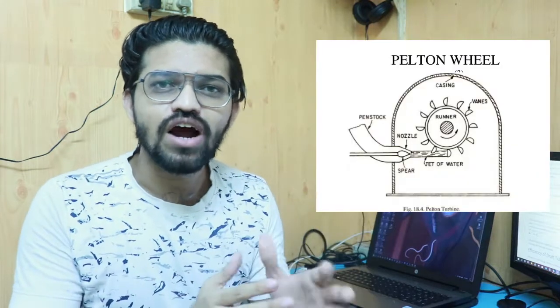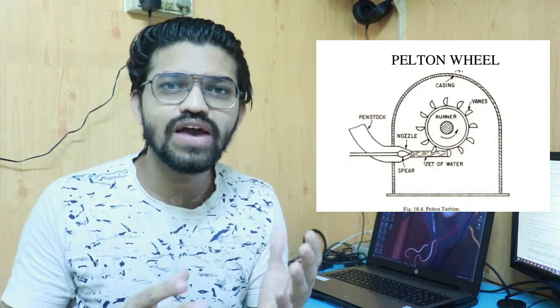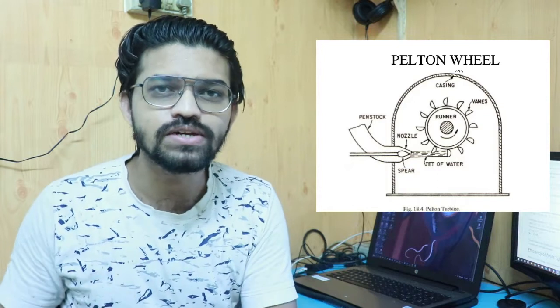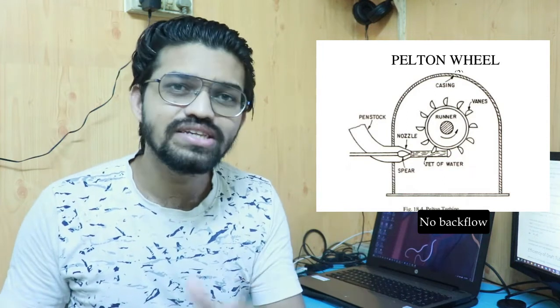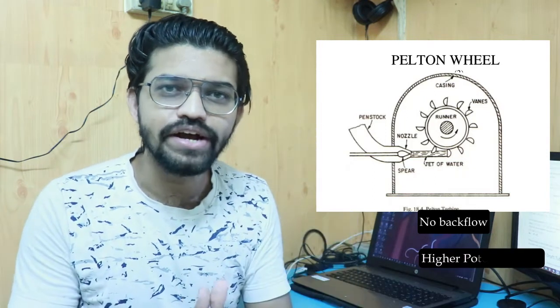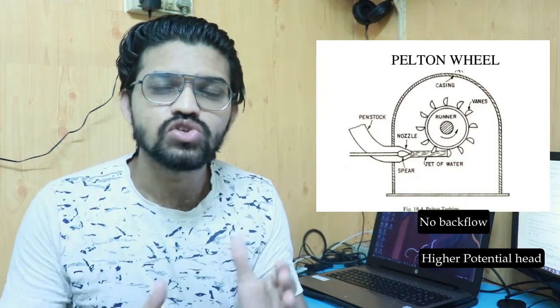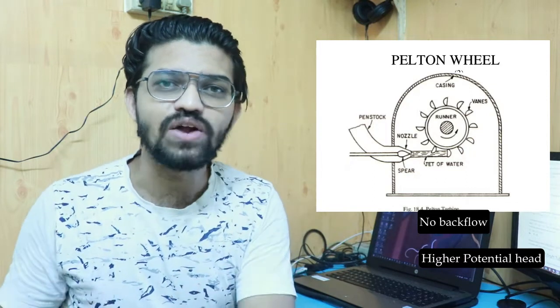In case of the impulse turbine, the draft tube is not needed. For a Pelton wheel turbine, there is a jet of water and the water gets drained into the tail race — there is no situation of backflow. Also, in the case of the impulse turbine, the available potential head of the water is much higher. These are the two reasons why the draft tube is not required for the impulse turbine.